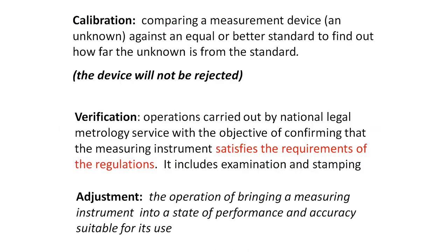And then there's calibration, verification, and a term that is used sometimes, adjustments. Verification and calibration, simply put, are basically the same: comparing your unknown with your reference standard, which is known. The only thing with verification is that it's a legal requirement. It has to satisfy the requirements of the regulation.